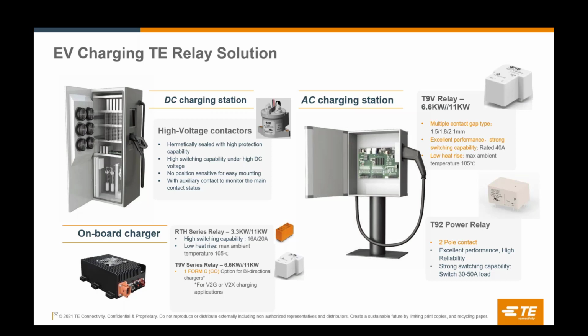Next up is 11 kilowatts, up to 48 amps now. We just released last year a special variation of our T92 relay called T92H. It's a 50 amp relay, each pole, it's a 2-pole relay, 50 amps. So this relay would cover the 11 kilowatt application. You only need one because it's a 2-pole relay.